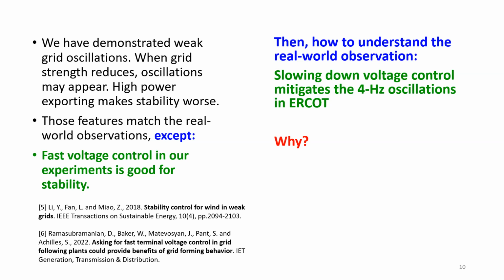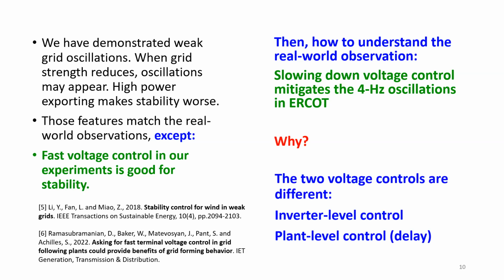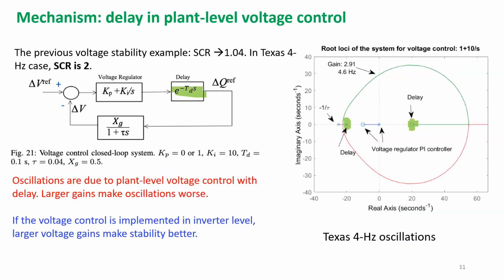So next, we finally find out that the two voltage controls are different. In our case, it's inverter level control. In the ERCOT case, it's plant level control. The difference is the delay: in plant level control, you cannot ignore the communication delay. So we re-examine this case and put the delay there, looking at the plant control.